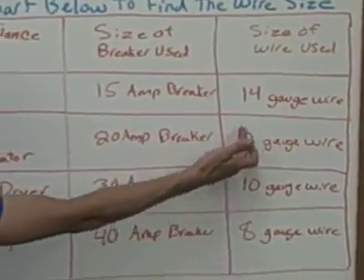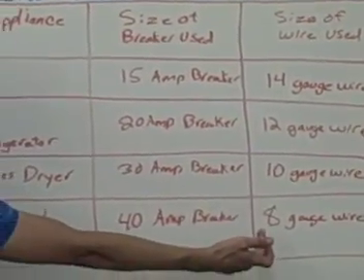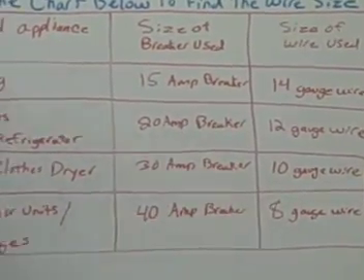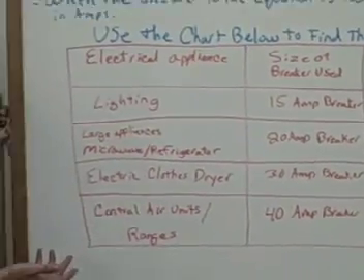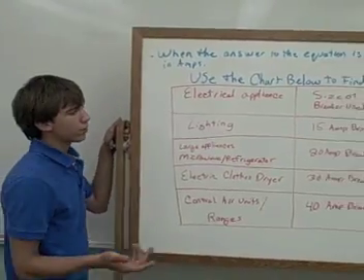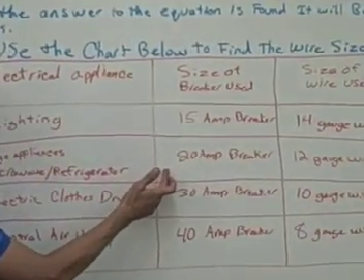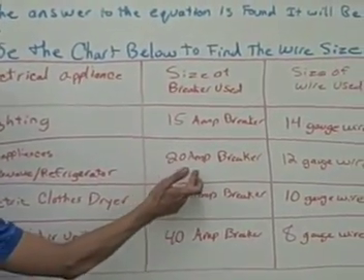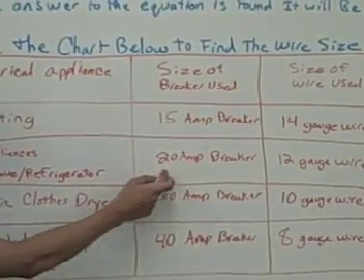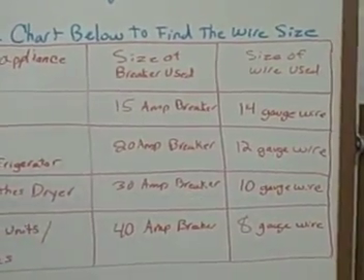Each of these, and the size of wire used in this column, corresponds to which breaker you would use with it. So when you find out that your microwave requires a lot more power — let's say the equation shows it takes up twenty amps — you're going to use a twenty-amp breaker in your panel in your basement, and you're going to use twelve-gauge wire.